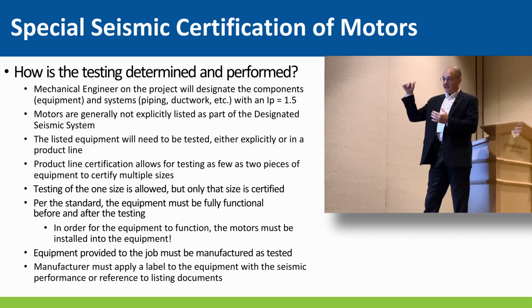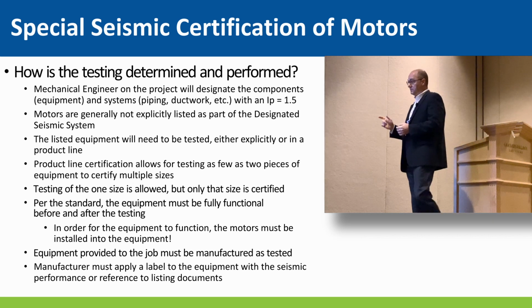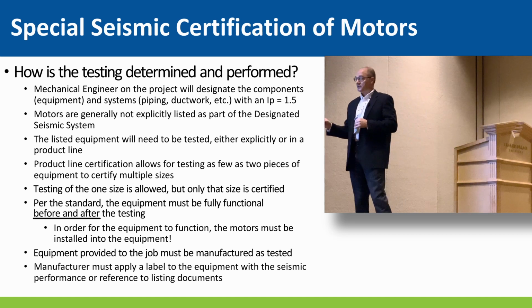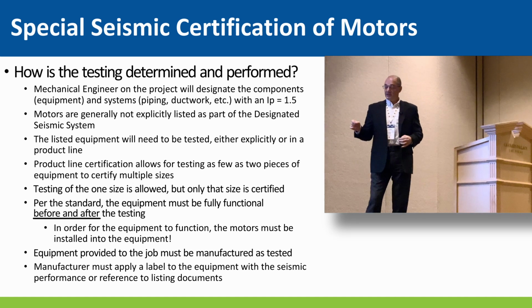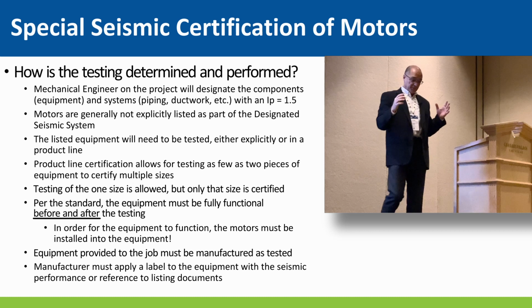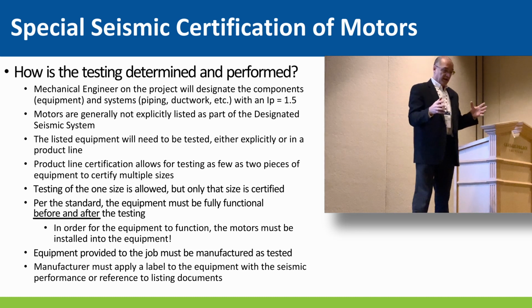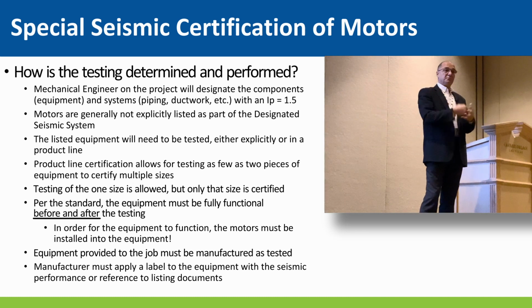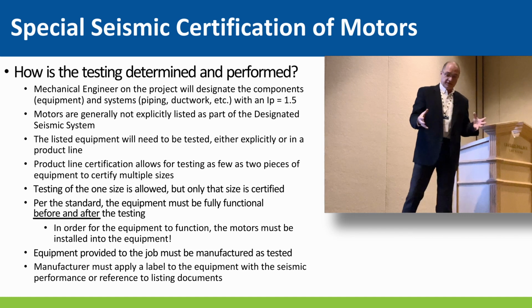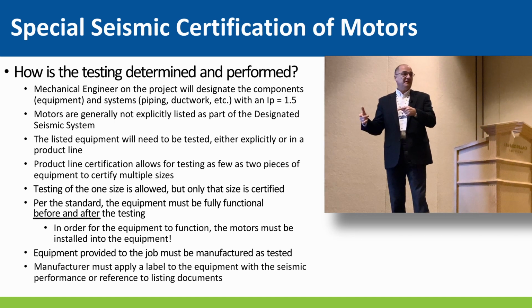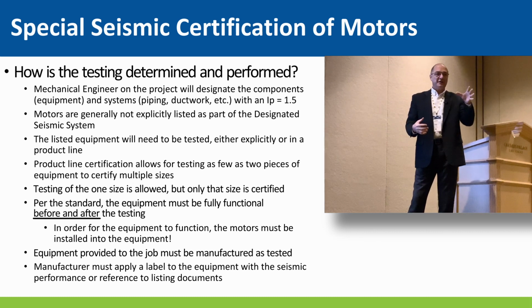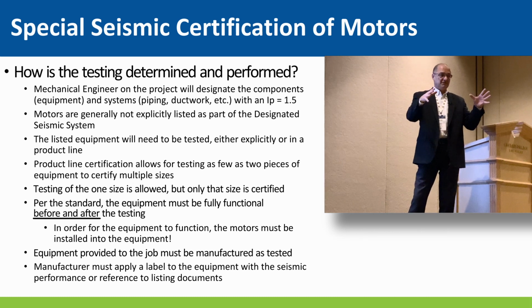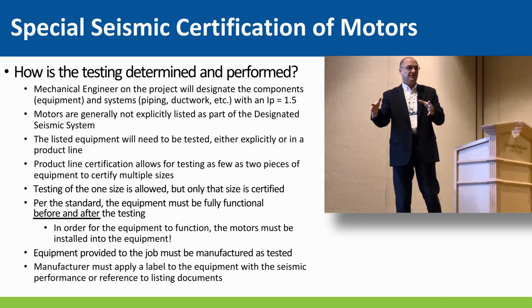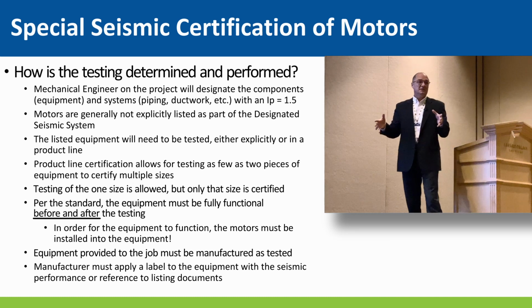Per the testing standard, the equipment must be functional before and after the earthquake. So think about it: the equipment that your motor is in, I have to test functionality. I have to prove it worked after shaking. If your motor wasn't in there, I won't be able to turn it on. So your motor may not be required to be tested per se, but it's got to be in the box to be tested, otherwise I can't turn on the box.